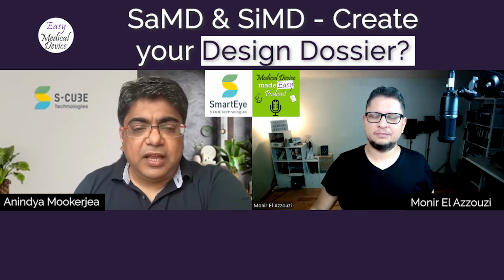A standard question. Everyone thinks, do we have to get an audit of 62304? Well, the answer is no. So far, it's not an auditable standard. However, it's so popular that if a person A says, well, I have got the best processes and activities in my product, I've got the best design file, and I have done a lot of work, but does not mention 62304, then I as an auditor will be more curious to know each and everything, because I will have an apprehension about the work.